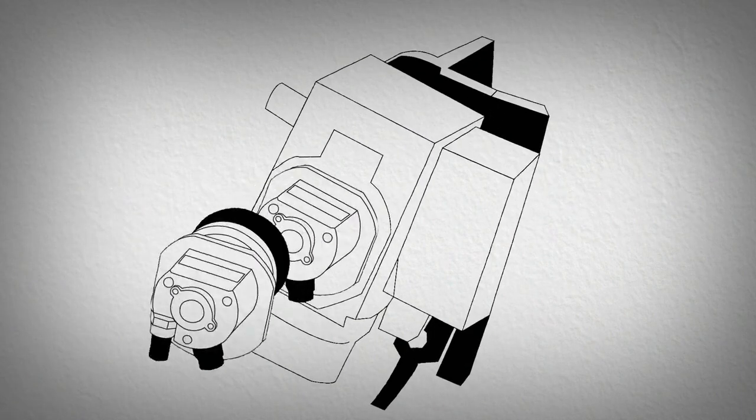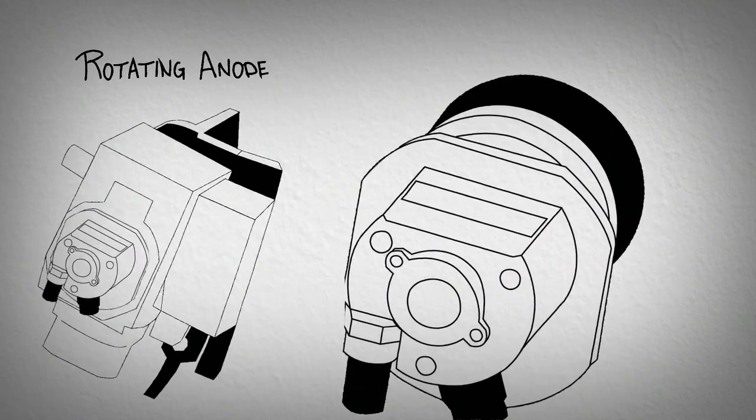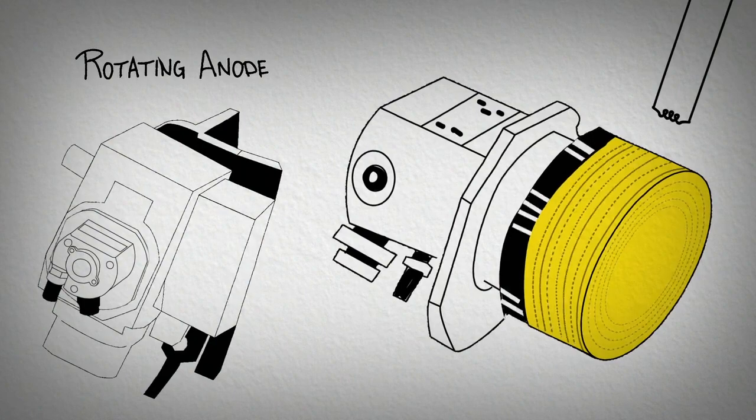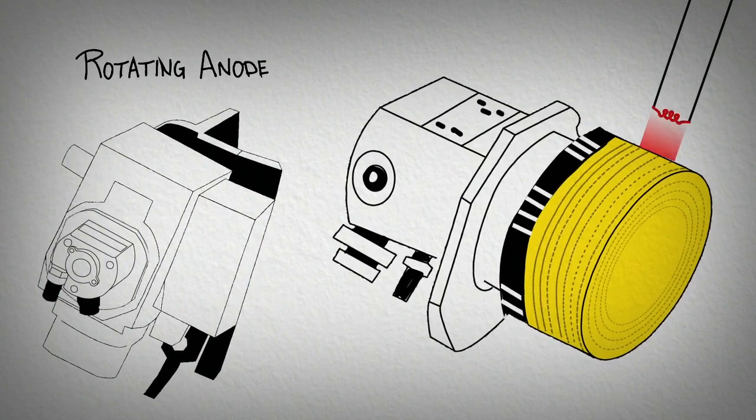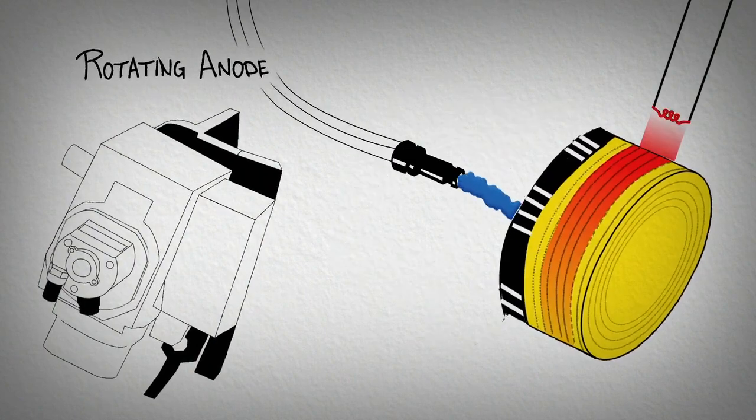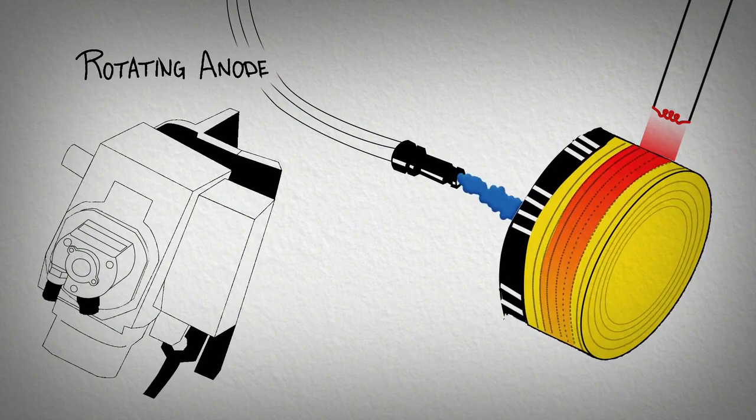If maximum signal is required, a rotating anode source is the best choice. The anode is spun at several thousand RPM in a vacuum chamber, evenly distributing the heat across the entire surface. Because of this, it can be operated at a much higher power level.